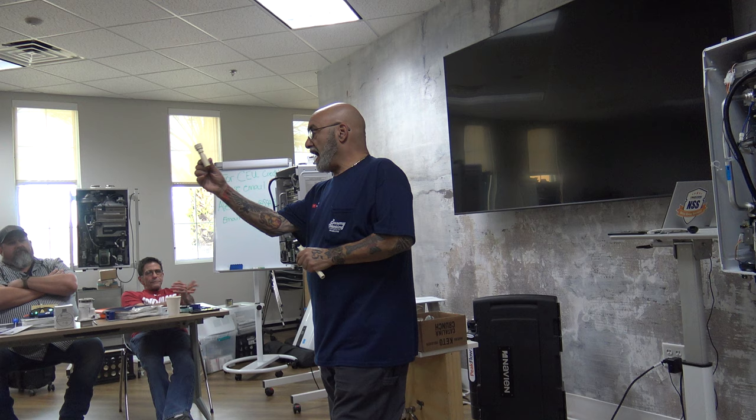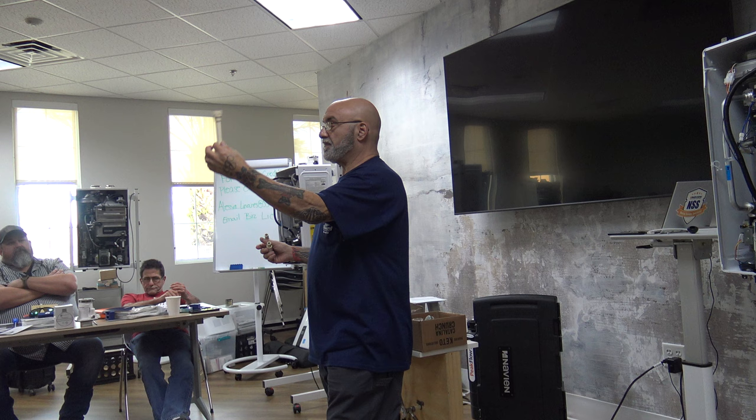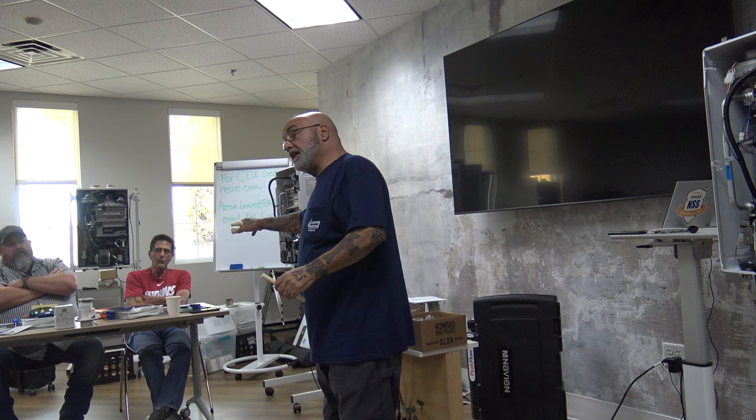So basically, it's this coming out of the bottom of the unit. Of course, longer, but that's it. You get what they call water lock, it's almost like a vapor lock or a vacuum. Now you say, whoa, it's just a pipe. And what he said before is, there's no drain. It's just flowing the stuff all over the electric, the water pipes, the insulation, the gas pipe, and it's rotting it away. It's highly acidic.